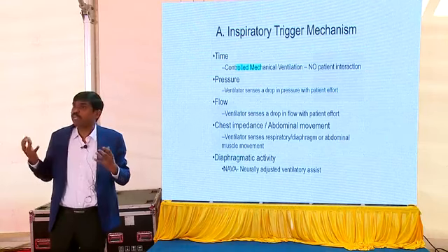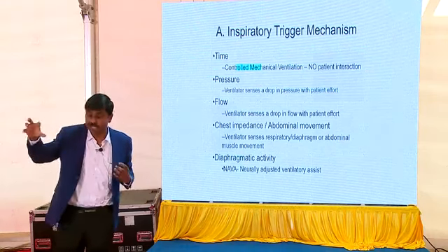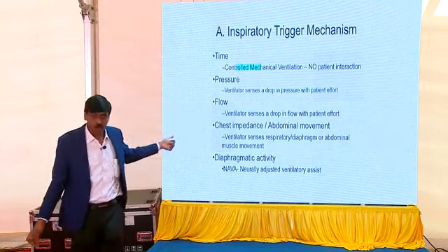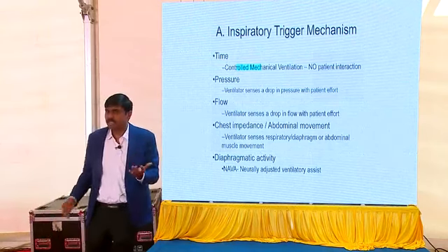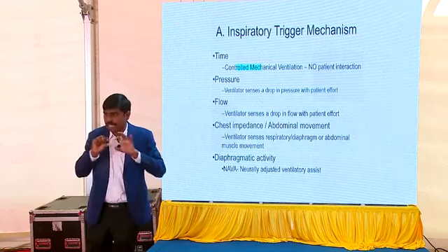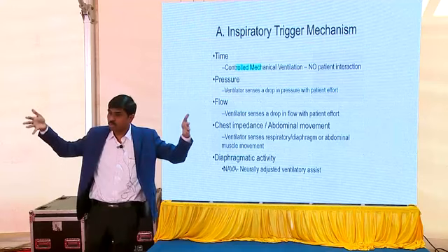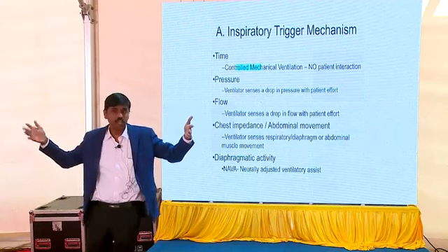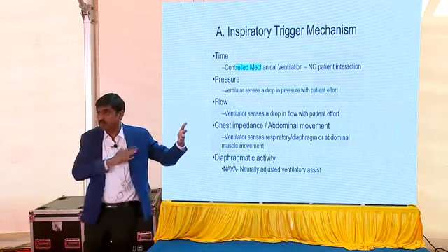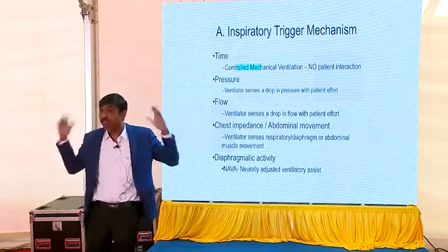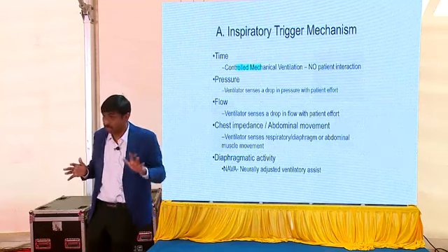a breath. Immediately the machine picks up, oh, this is a breath, let's start the inspiration. Next, there is something called flow. Now, how flow basically works is there would be a heated coil inside. Imagine a heated coil with a temperature sensor at both ends, and imagine there's just a whiff of air. What happens? Temperature immediately drops at the distal end.